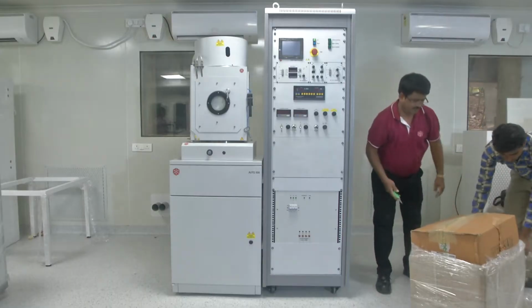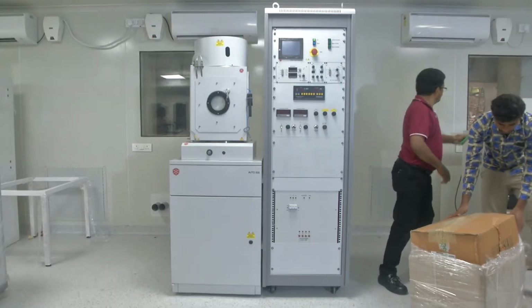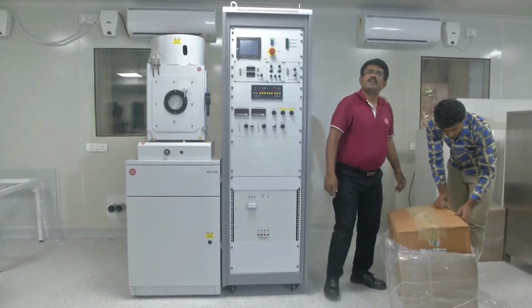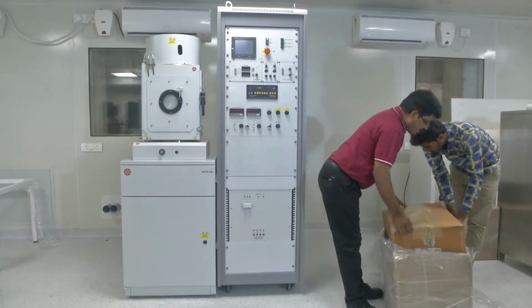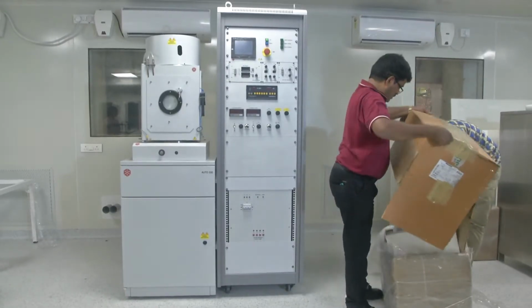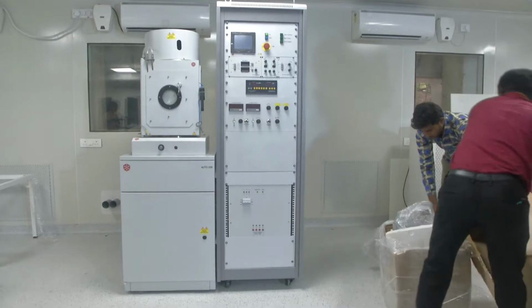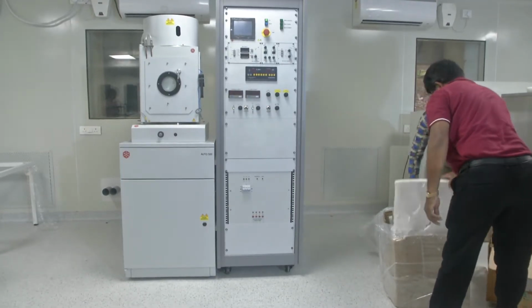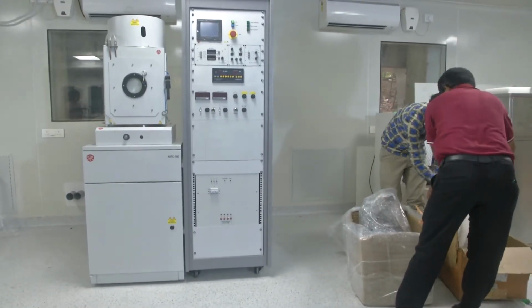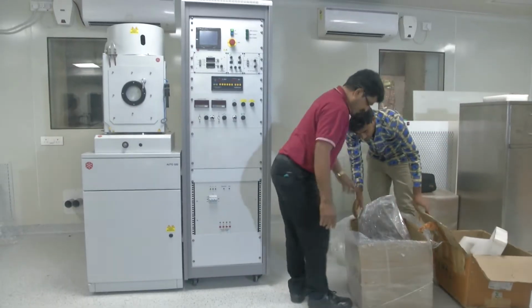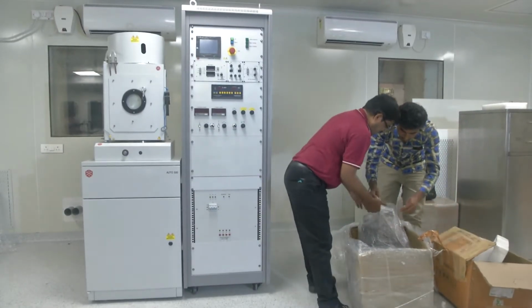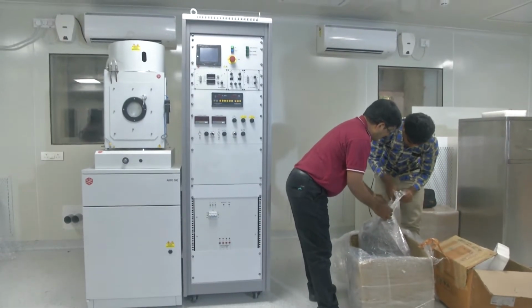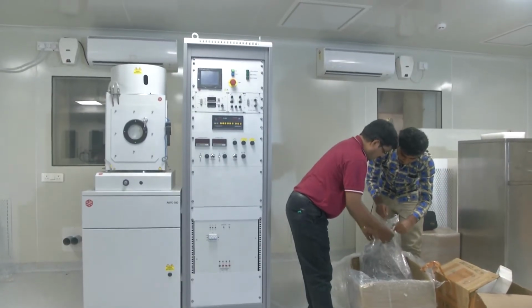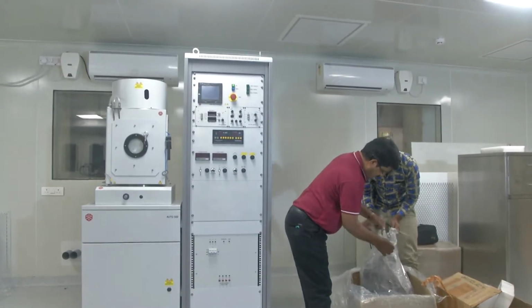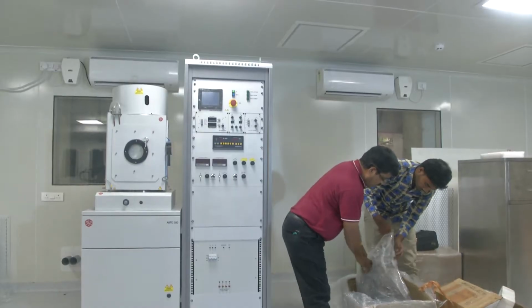So for the system, we need two main additional things, which is a chiller unit and a compressor unit. The chiller unit will be filled with DI water, deionized water. That will basically be used for cooling purposes, not inside the chamber, but around the chamber, so that temperature control can be done. And the compressor unit, as you know, would be used for flushing in air, taking out air, creating vacuum and all those purposes. So now they are unpacking the compressor unit which will be installed.